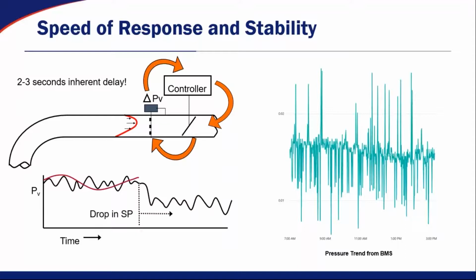However, when you have a rapid drop in static pressure, say when a building goes from unoccupied to occupied mode, you're going to have a large drop or a longer time for that device to actually catch up to that drop in static pressure.